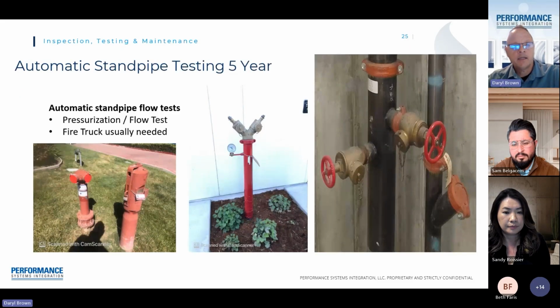So that kind of clears what we do during a 5-year on the sprinkler system. A standpipe system also has some additional requirements every 5th year. As I said before, these standpipe systems are utilized by the fire department to verify that if they need water at a remote location, this is where they hook their hoses up to actually obtain water.